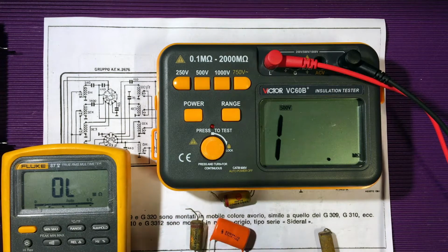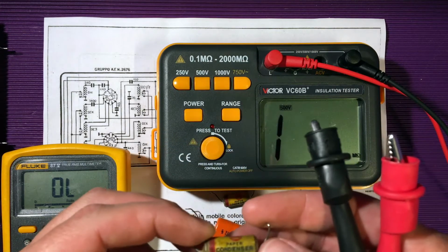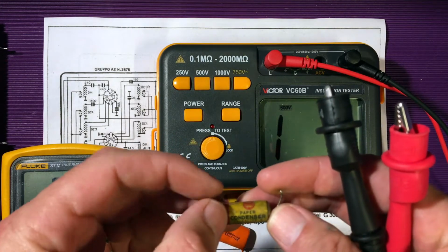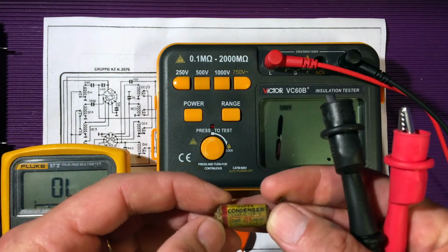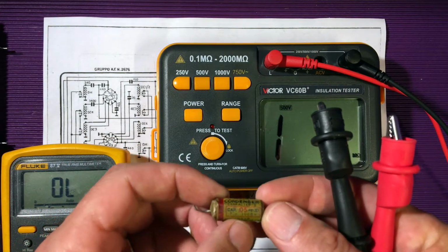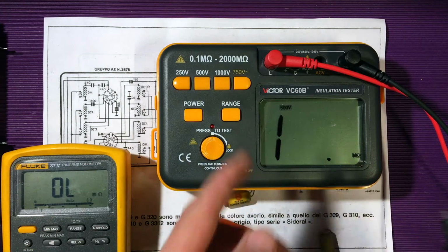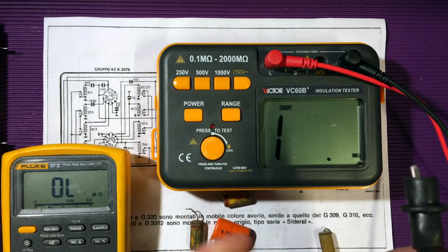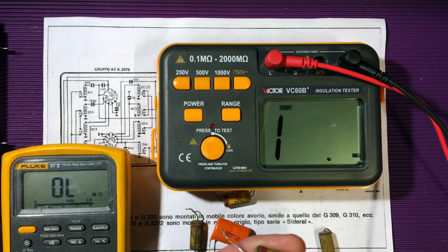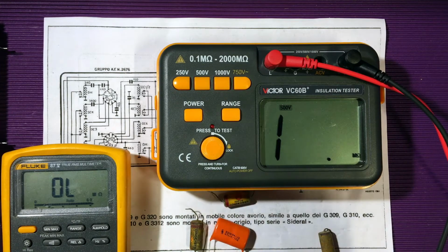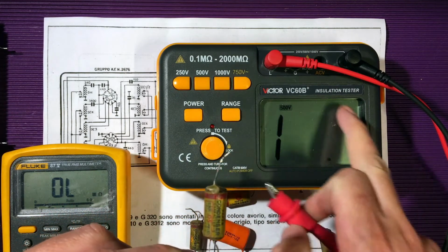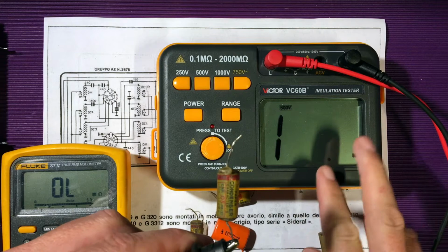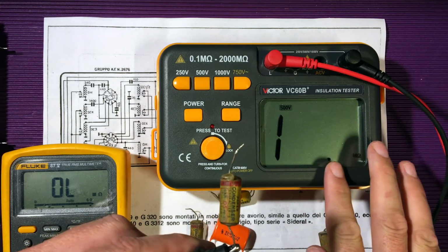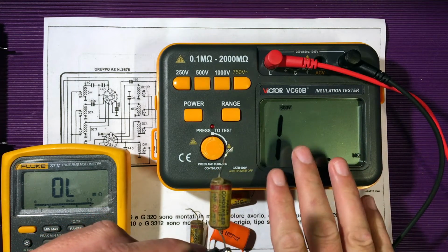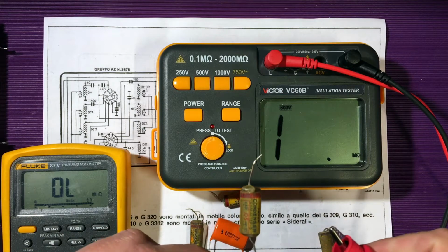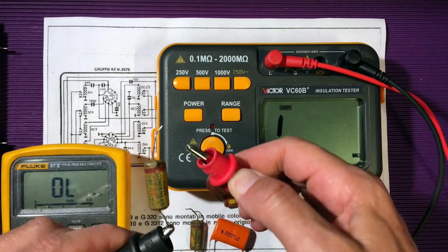Since these are high voltage paper capacitors, paper condensers, and they are 1000 volt rated, I will measure them with 500 volts. This charges, it should charge, so the value should start very low and then drift until it gets to infinite. That's the behavior it should have.